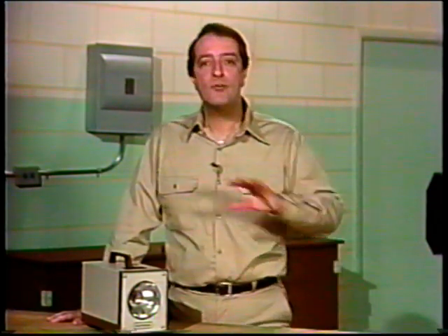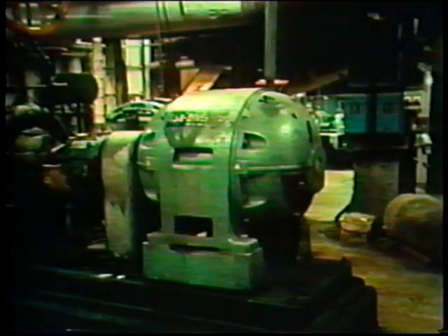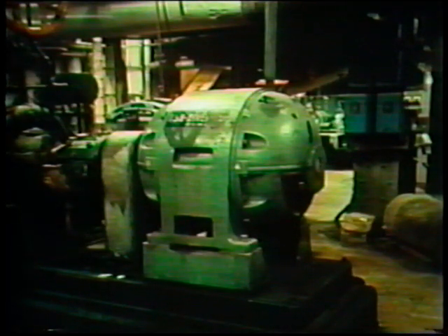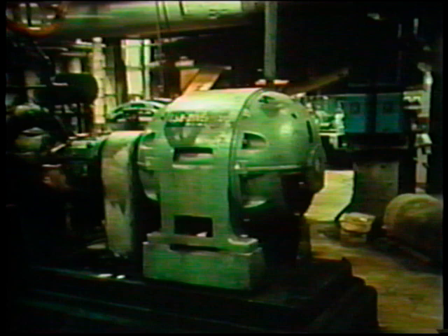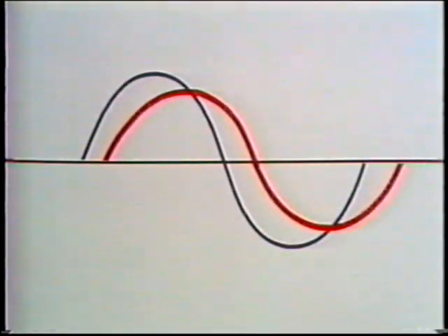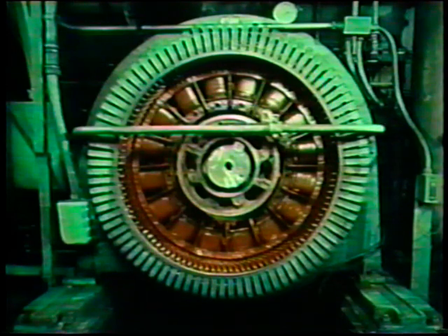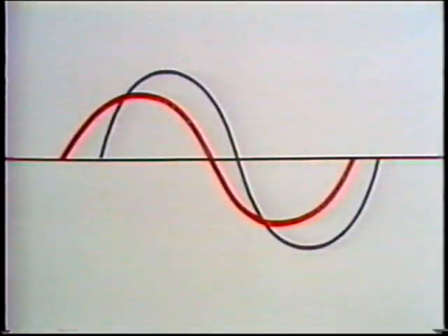By adjusting the power factor of synchronous motors, the overall electrical efficiency of an industrial operation can be improved. How is that possible? Well, an industrial plant uses many induction motors, transformers, and other equipment that have a low power factor. They cause current to lag behind voltage. This causes an overall electrical inefficiency in a plant. Overexciting a synchronous motor counteracts this effect. Overexcitation causes current to lead voltage.